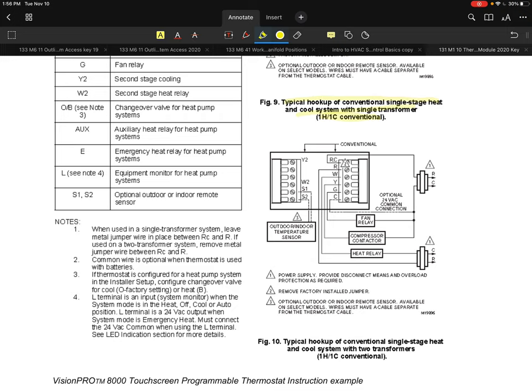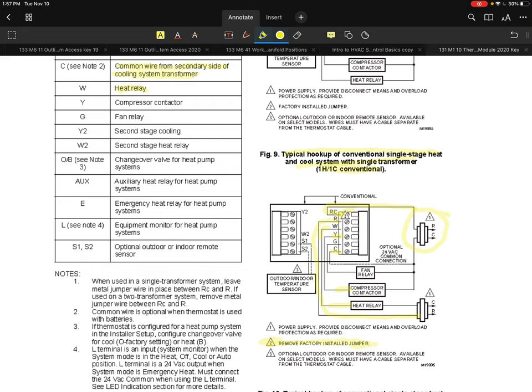For a two-transformer system, remove the factory-installed RH-RC jumper. One transformer handles cooling via RC and the other handles heating via R. The thermostat is smart enough to use the correct power source for each mode — RC powers the compressor contactor Y when cooling, and R powers the heat relay W when heating. Additional terminals include Y2 for second-stage cooling, W2 for second-stage heat relay, and G for the fan relay.